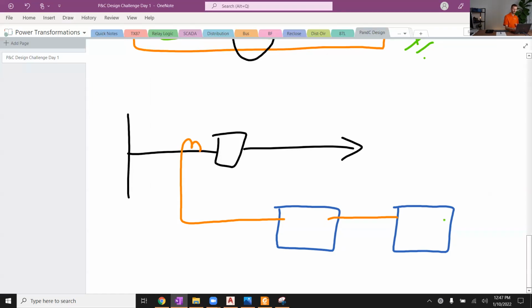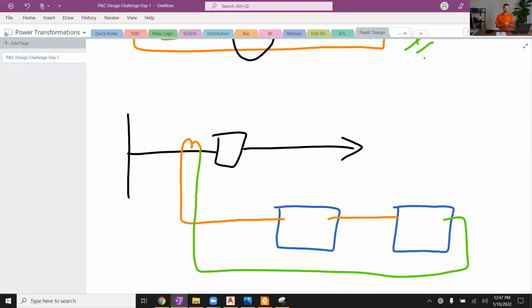You would tie them together and you would have a neutral coming back around here on relay 2. So you'd have 3 wires coming into relay 1, 3 wires coming out going to relay 2. And then on the non-polarity dots of relay 2, you would jumper them together to make a neutral common and bring that return path back to the neutral of your CT.